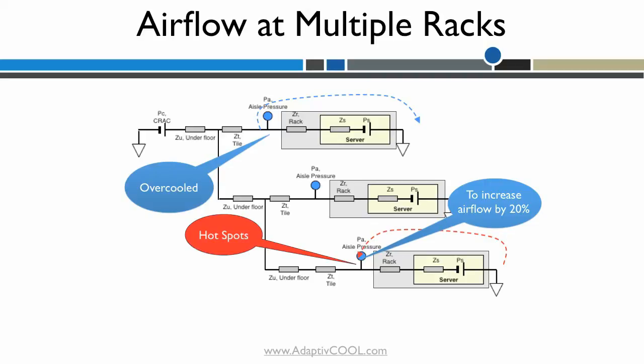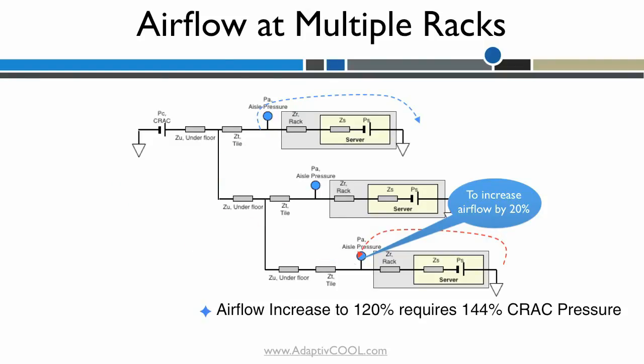Since the pressure required is the square of air flow, to achieve 20% more air flow, the CRAC fan pressure output needs to increase by 44%.